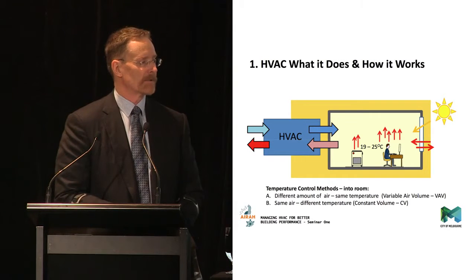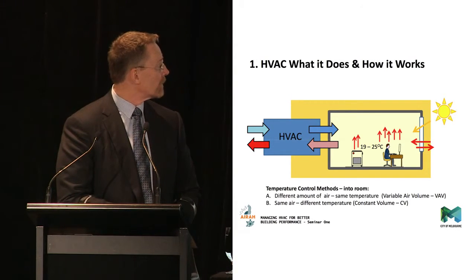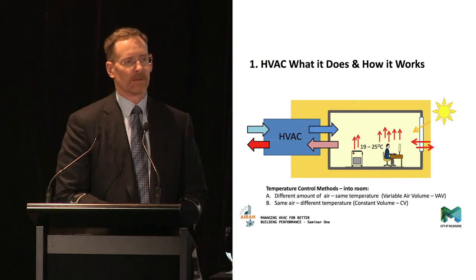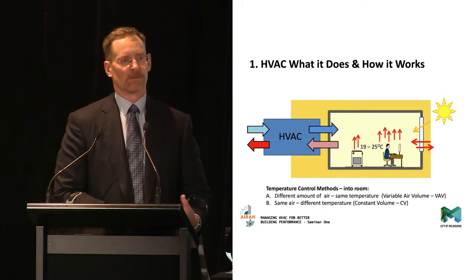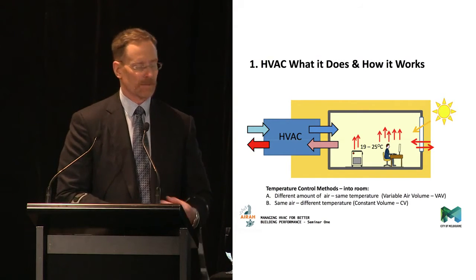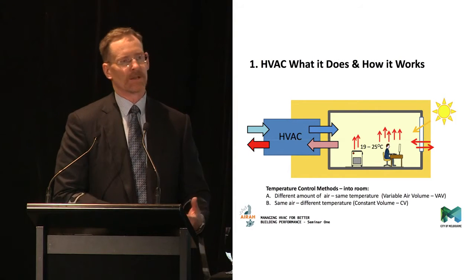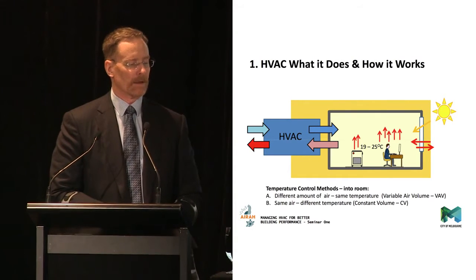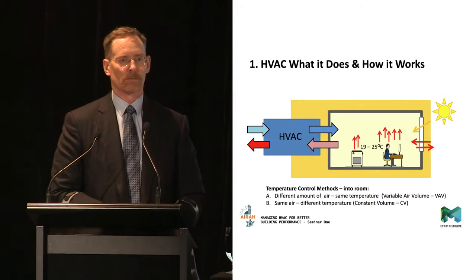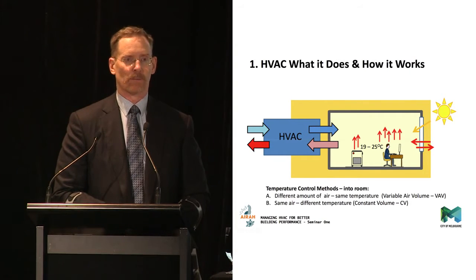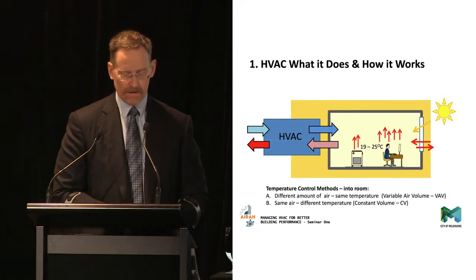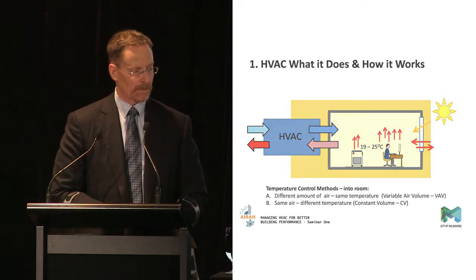There's two ways that happens, basically. You either vary the amount of air coming into the room at the same temperature, or you change the temperature of the air coming into the room. This will become important a little bit later on. So we start to introduce terms like variable air volume and constant volume. I'm sure a number of you have heard the term VAV and VAV boxes. Pretty important thing when it comes to maintenance. But anyway, let's just dip up a little bit from that.